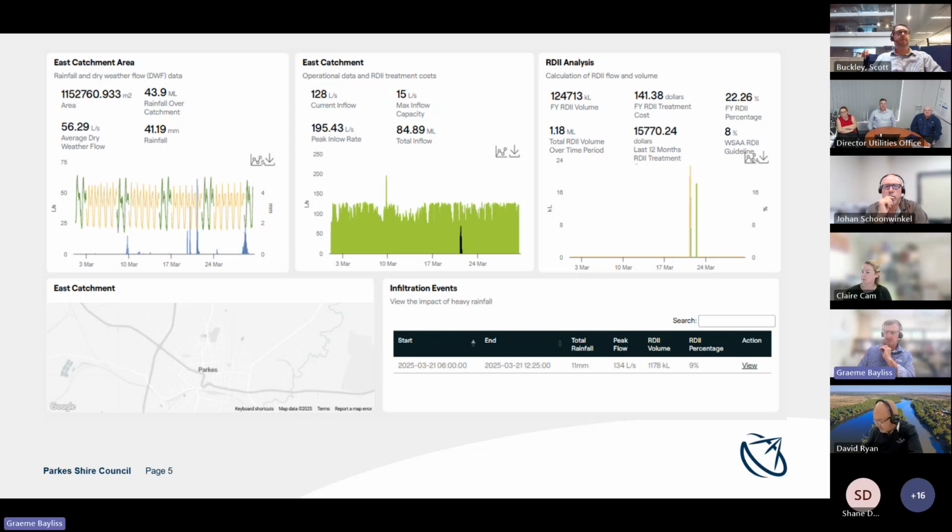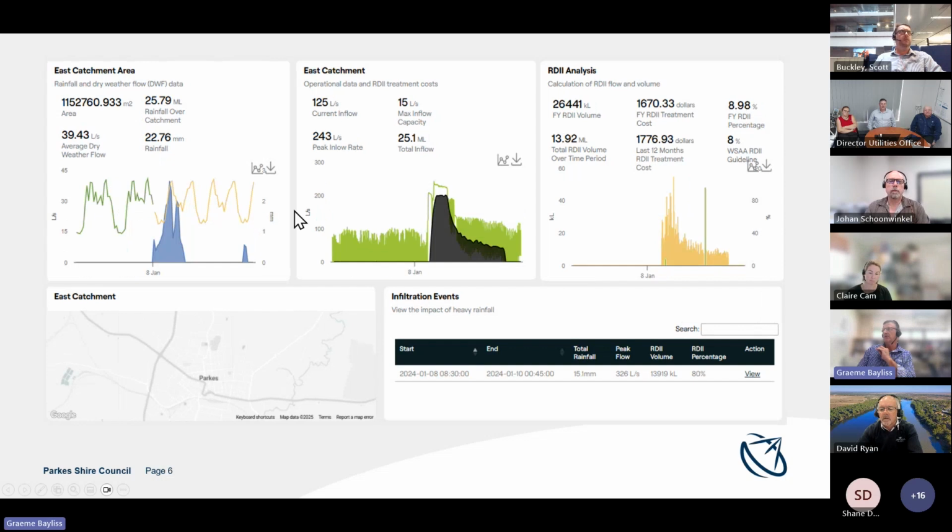Back in, let's try and get the date again, back in 24, you can see we had not a very big rain event, 20 mil, I think it was, in that period. And you can't see on this table, but we had 12 meg of effluent coming into our system when we normally only have 2 meg a day coming in. So it was like a massive rain event that resulted in massive flows being received.